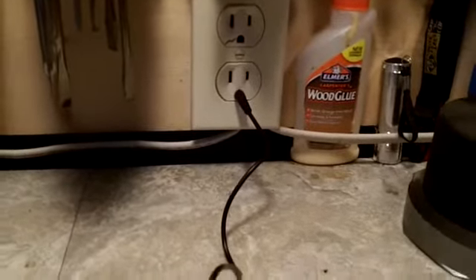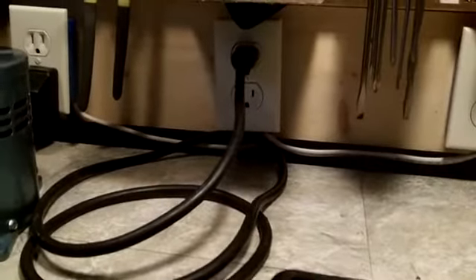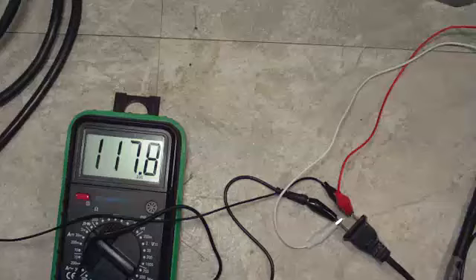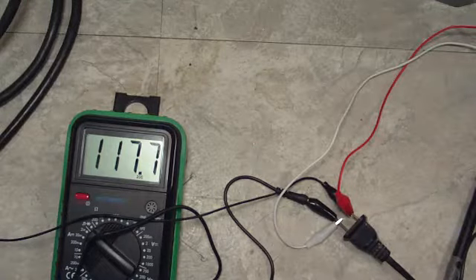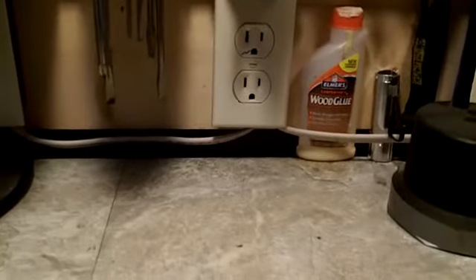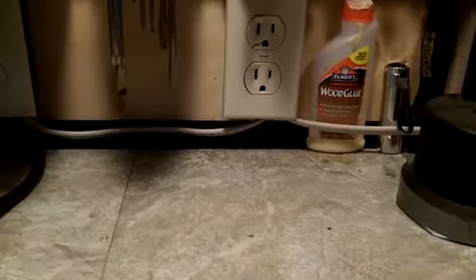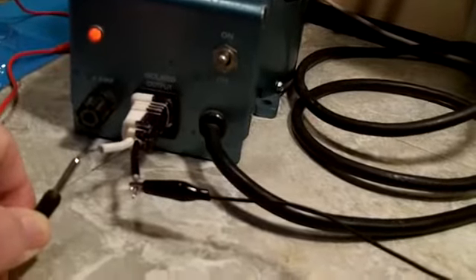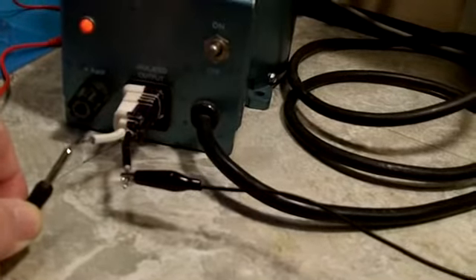I'm going to show you what happens when we remove the ground plug from here and connect over here - oh yeah, there you go. There's your voltage. So you can see there's no connection from the isolation transformer to ground. That's the thing we're trying to avoid, and that's what the isolation transformer does: keeps you from having a shock potential on whatever you're working on.